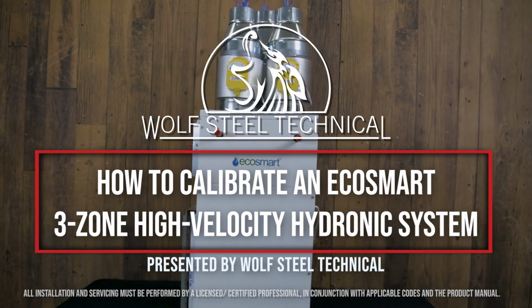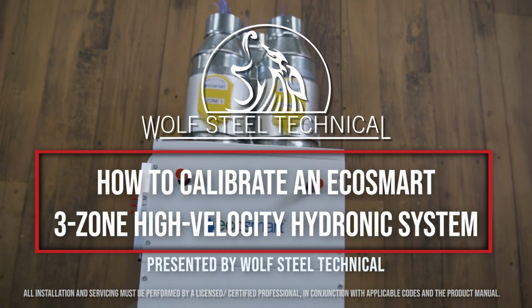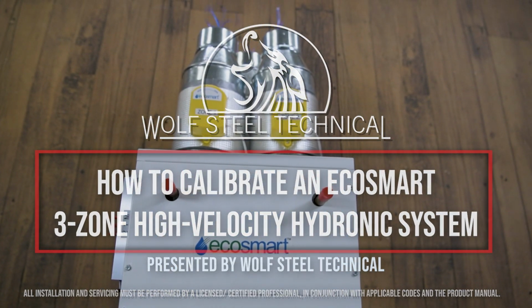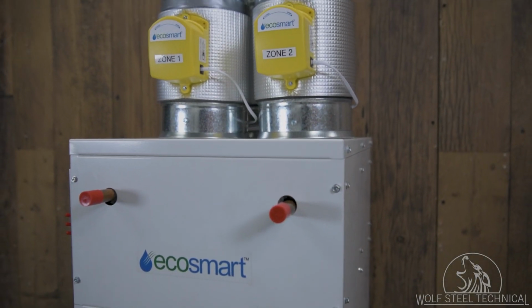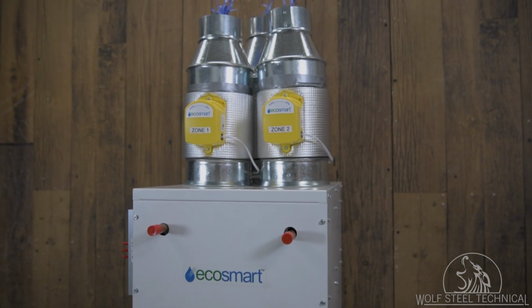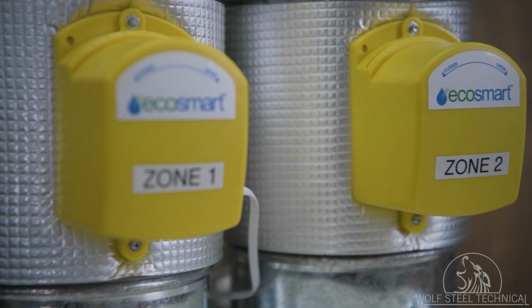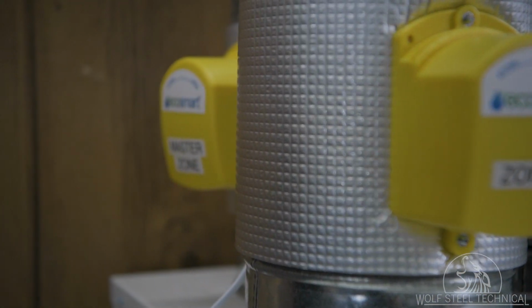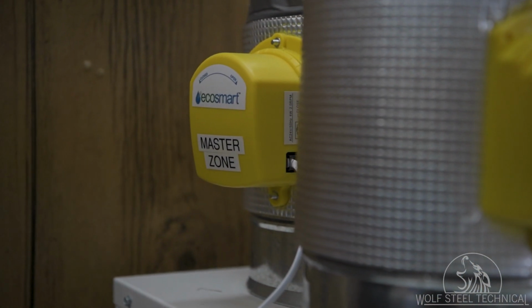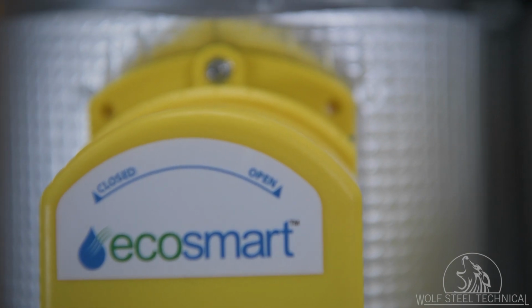This video includes a demonstration of how to calibrate an EcoSmart 3-zone high-velocity hydronic system. The EcoSmart system uses constant pressure technology, known as CPT, to maintain the desired airflow within the ductwork, irrespective of zones or outlet vents opening and closing. This reduces the potential of airflow noise and reduces energy consumption.